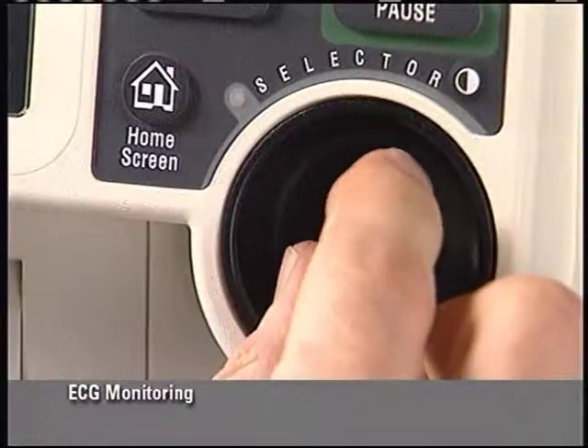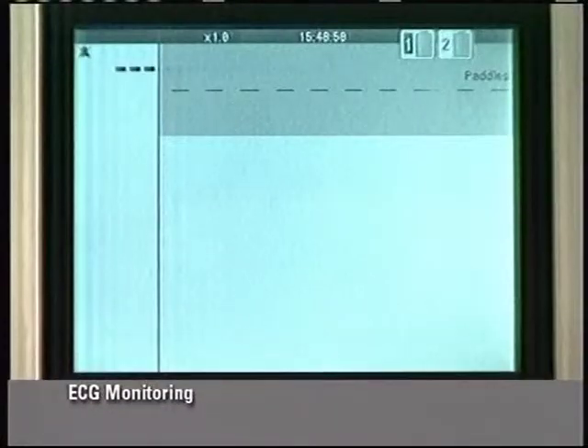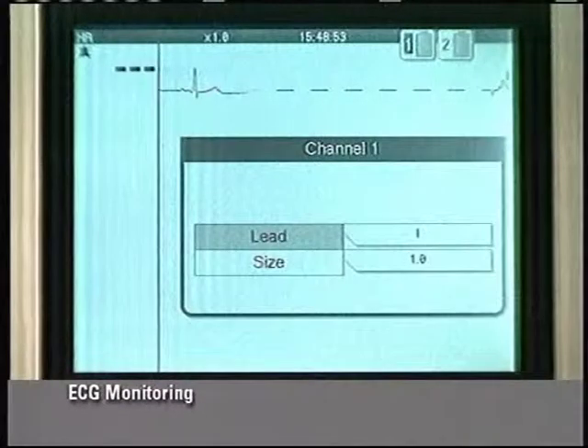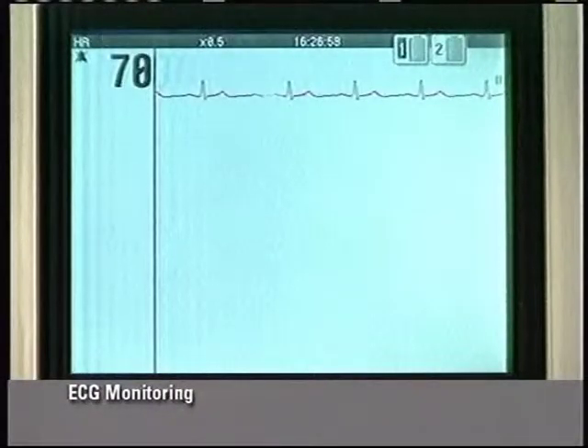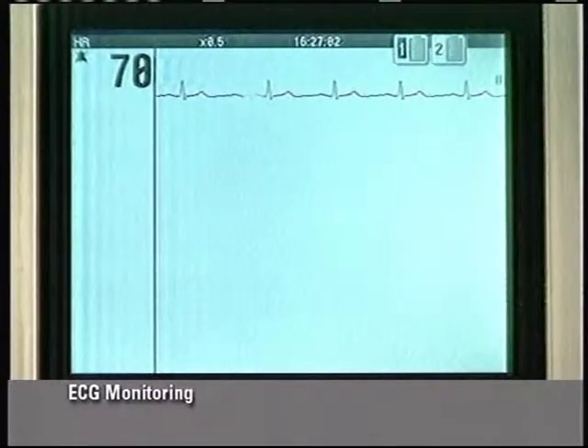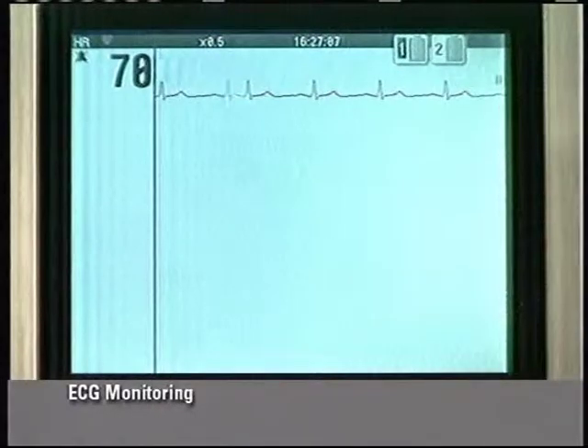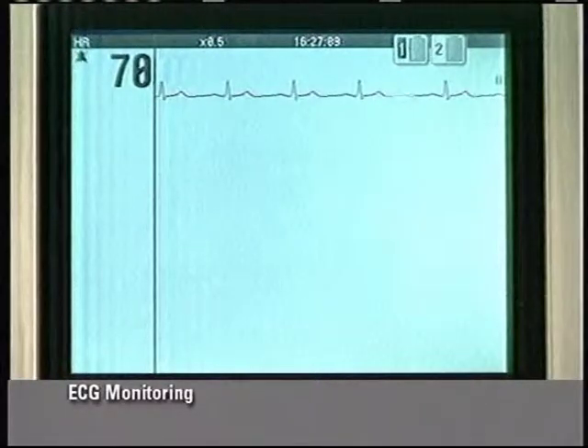Alternatively, you can use the selector to highlight channel 1 and change the lead. Check that the ECG size is adequate for heart rate counting. If the ECG size is too small or too big, heart rate counting may be inaccurate. The heart symbol should flash, and the systole tone should sound once with each QRS.